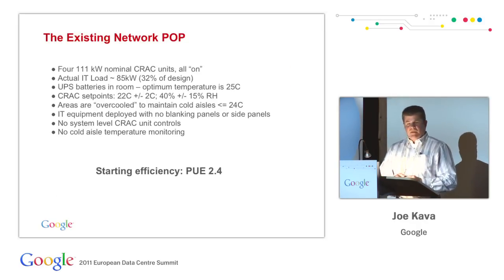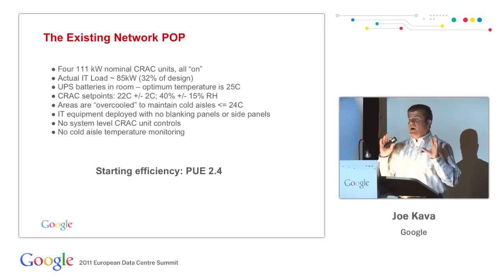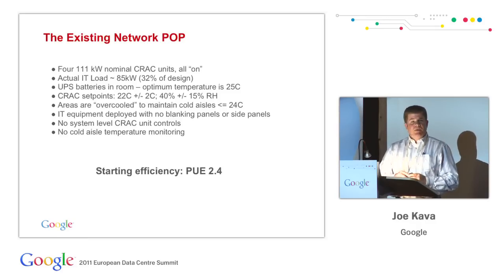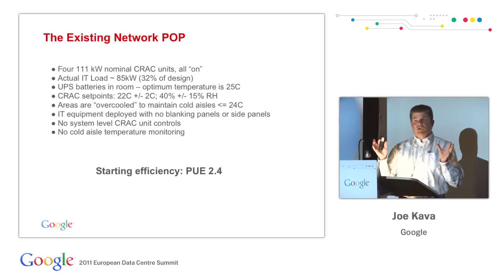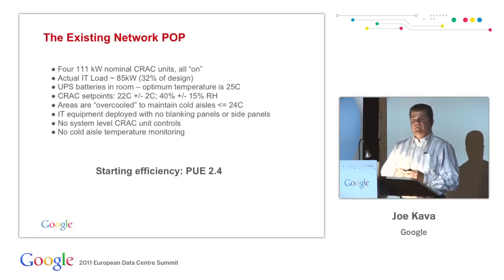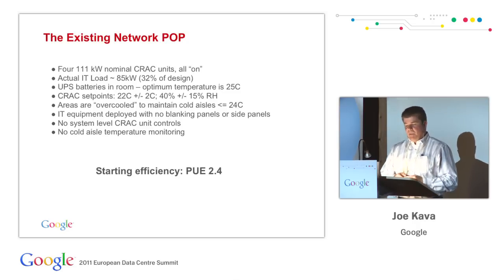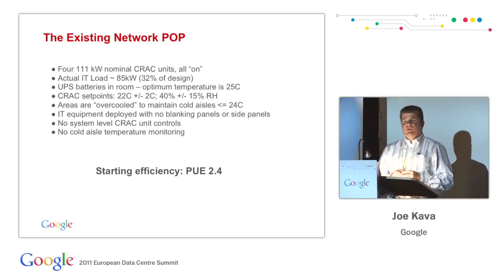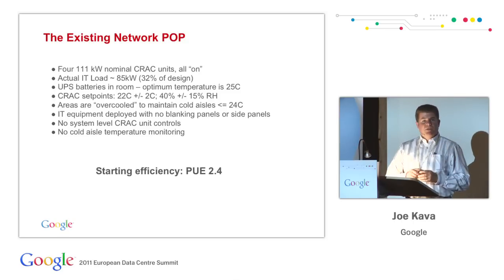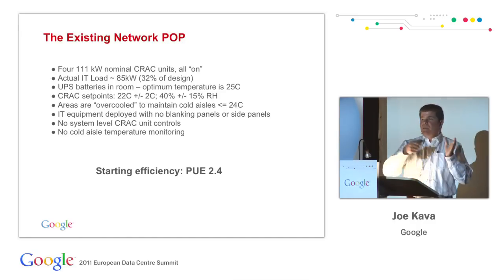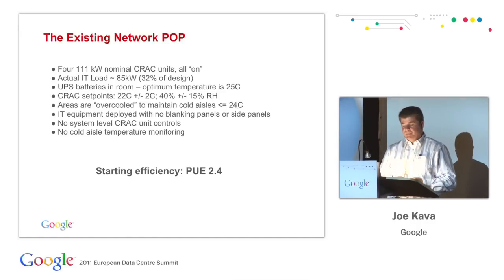They were way overcooled. There were multiple redundant CRAC units, all of them on all the time. UPS batteries were on the floor, and of course the UPS batteries require temperature control, stringent temperature control to maintain the availability and reliability of those UPS systems. So they had to be maintained at less than 25 degrees. There was lots of air mixing. As you can imagine from the picture we just saw, there was not good deployment of hot aisle, cold aisle separation. The general best practices that we've talked about this morning that everybody knows weren't implemented properly.